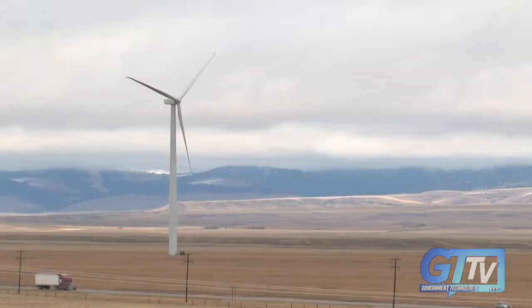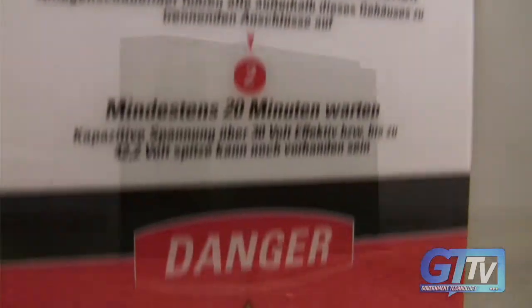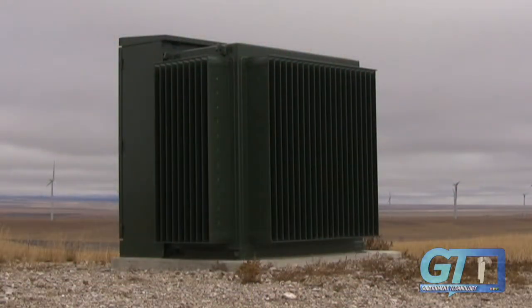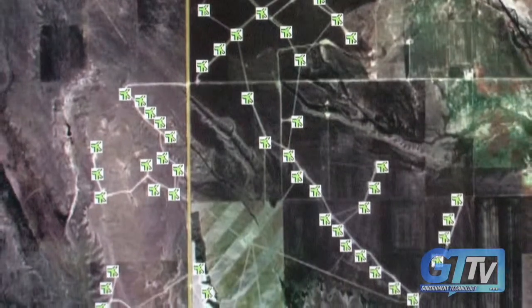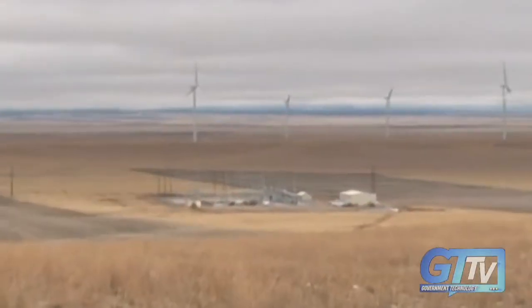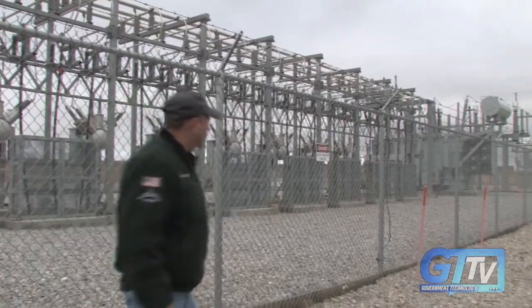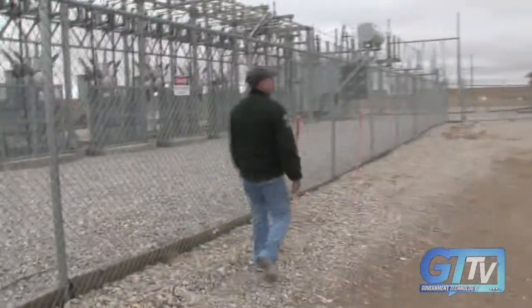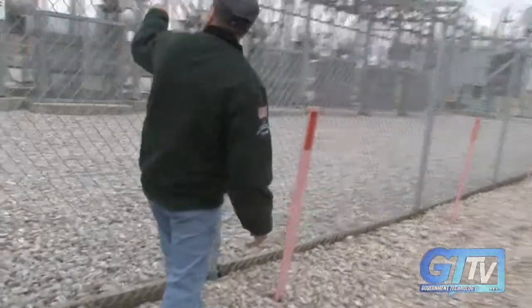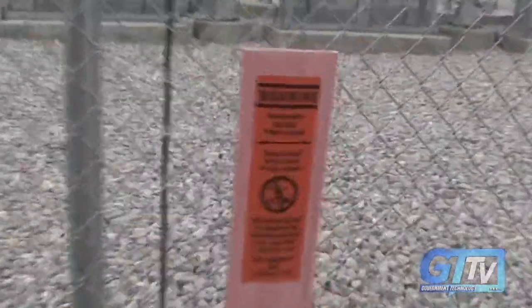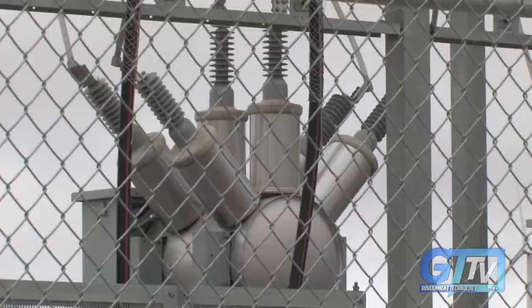The turbine produces power at 600 volts AC. It comes down those cables on the back wall and into this box, where we step up the voltage to 34,500 volts. There are only 7 main feeder circuits, so you've got 12 or 13 turbines per feeder, and we run underground cable all the way back to that substation, which all feeds in right back here. Each one of these is a cable location coming in, feeding into a circuit, which you can see the 3 cables coming up right there, and then it all shoots down that way.